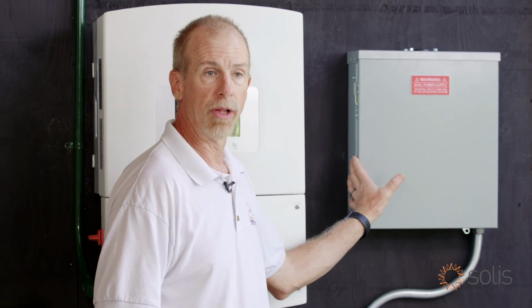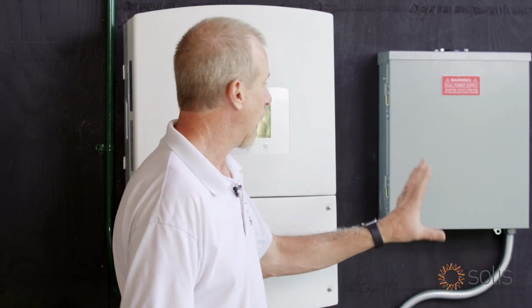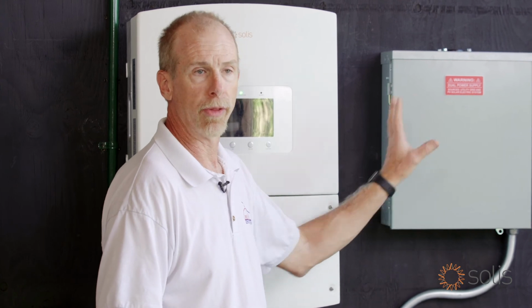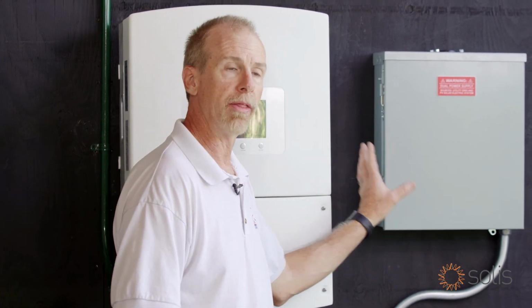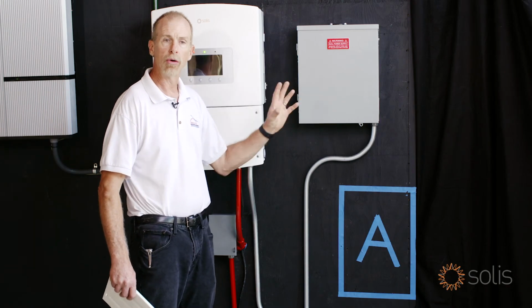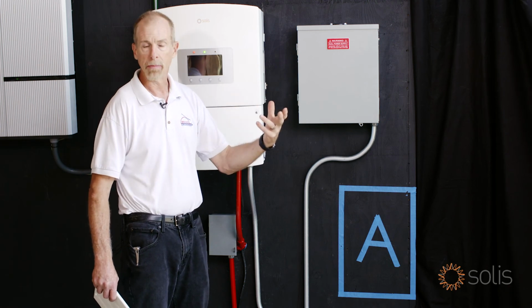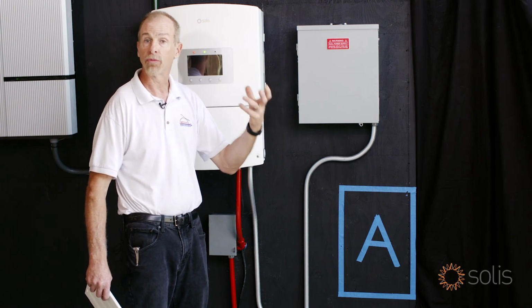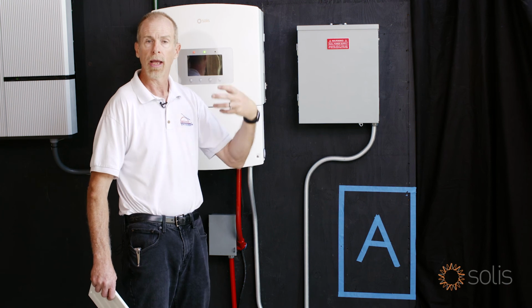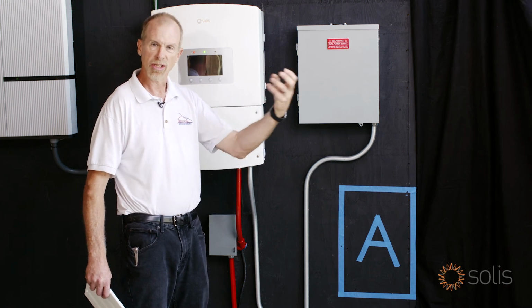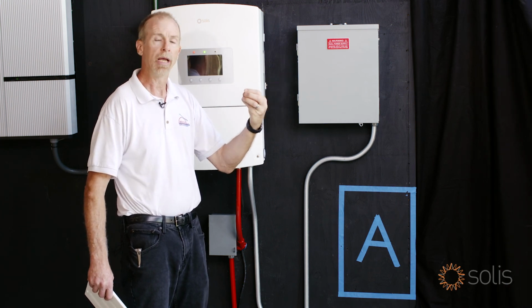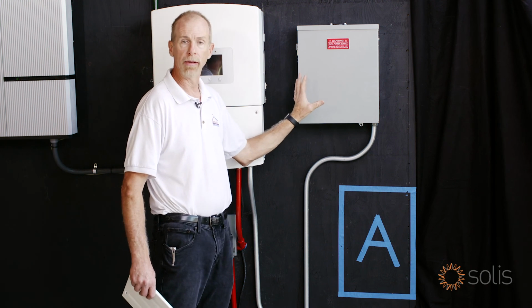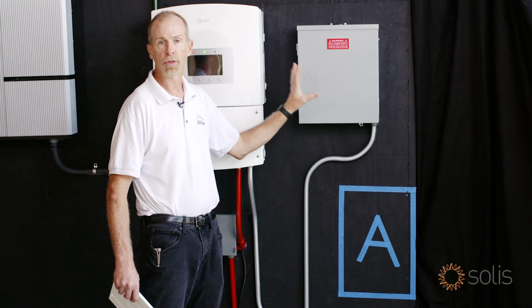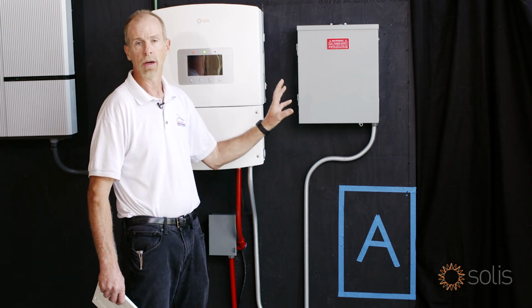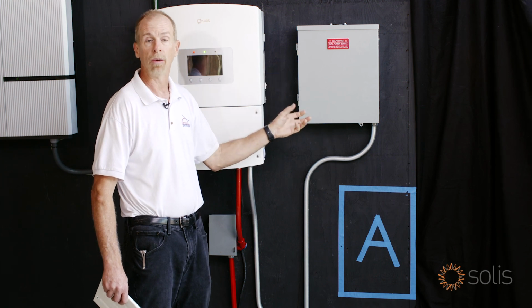This is our backup loads panel here. Now we've just physically put it here for the purpose of doing the video, but normally this backup loads panel would be located next to the main panel for the house, where we're going to be selecting loads out of that panel, selecting circuit breakers out of that panel, and we're going to put those circuit breakers in the backup loads panel for the circuits that we want to operate when we need backup power when the power goes out.